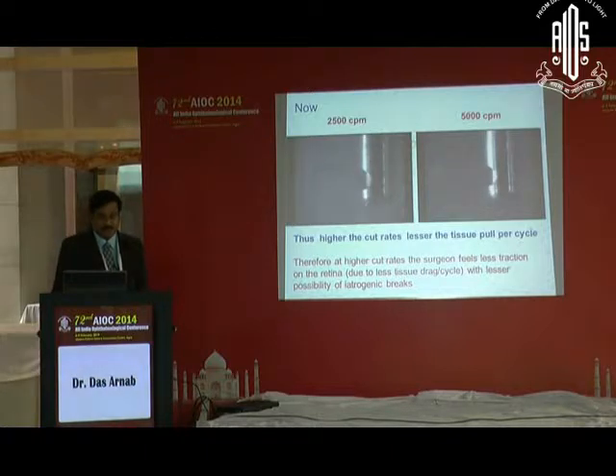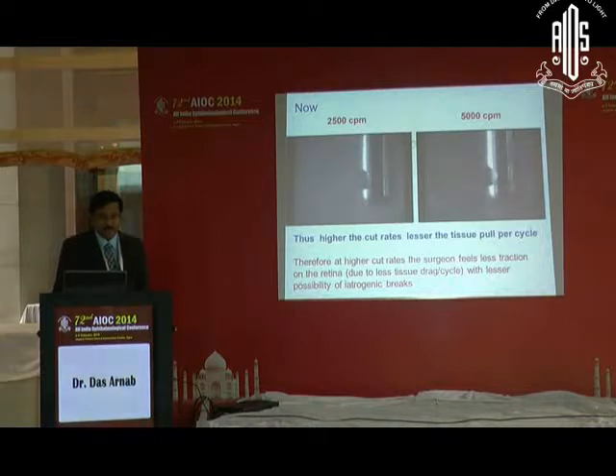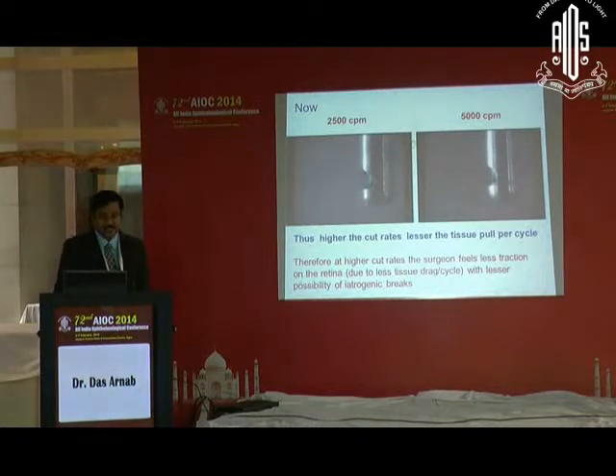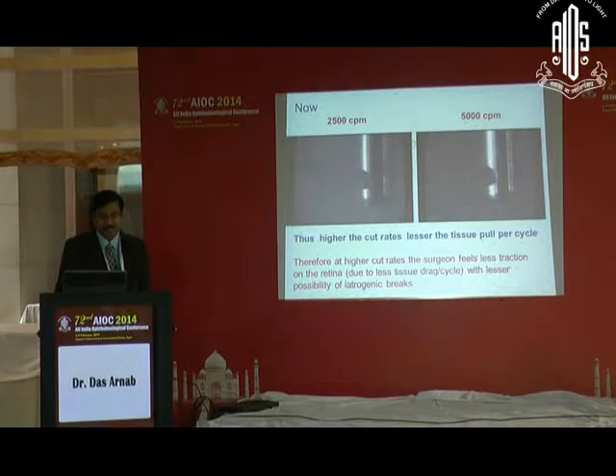Obviously, at higher cut rates, the lesser the tissue movement per cycle. Therefore, at higher cut rates, the surgeon feels less traction on the retina due to less tissue drag per cycle, with lesser possibility of iatrogenic breaks.